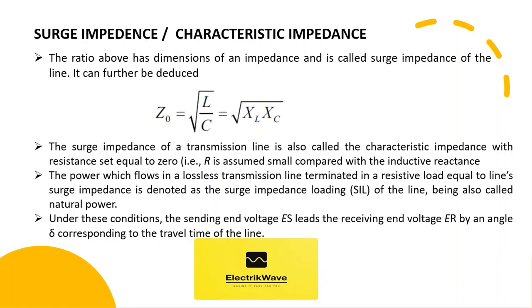The characteristic impedance, or surge impedance of a uniform transmission line, usually written Z0, equals square root of L/C, equals square root of XL times XC. The surge impedance of a transmission line is also called the characteristic impedance with resistance set equal to 0, that is, R is assumed small compared with the inductive reactance.